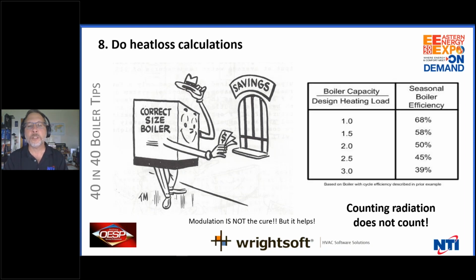You know, if your boiler is twice the size it needs to be, it's running at 50% its efficiency. So you put a cast iron on-off boiler into someone's house. If you exactly size it for a 14-degree day in Philadelphia, that means when it's 39 degrees out, you're only going to be running at 40 some odd percent efficiency because of short cycling. A modulating condensing boiler's not going to do that, but that's no excuse to not do a heat loss.